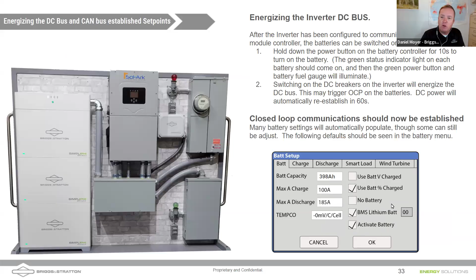Now we're continuing, still on the BAT tab, and we're also looking at setting the battery capacity, which should be automatically populated, as well as the max amp charge and discharge here. There's a chart over on the right-hand side. Let's use the Sol-Ark 15K, for example, with a stack of three 6.6 modules. You can see the discharge is 273 amps. The Sol-Ark 15K can do 275 amps, so you come in here and put in max discharge 273.